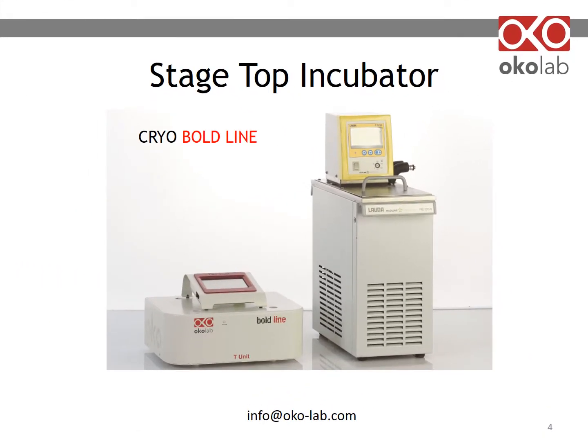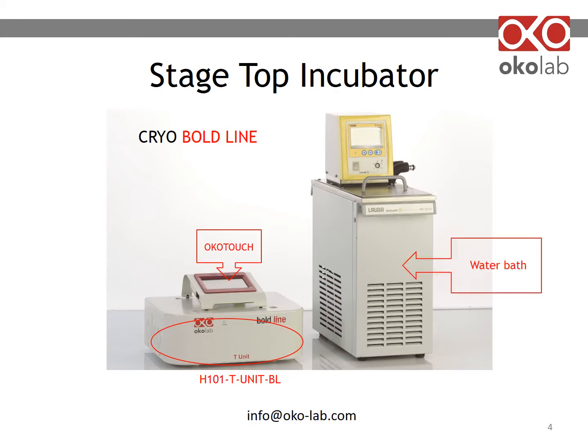This slide shows a cryo-boldline water jacket heating and cooling system. On the left is the temperature controller with its touchscreen interface OkoTouch. On the right you can see the water bath. Depending on the temperature you need to reach, you may have to use a liquid other than water. Contact OkoLab at info@oco-lab.com for more information.